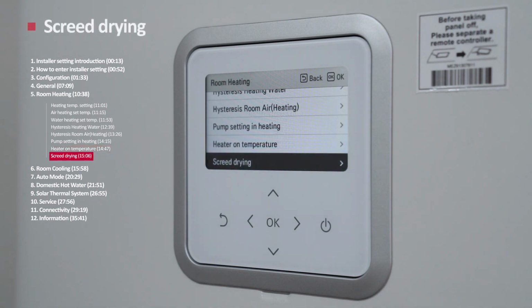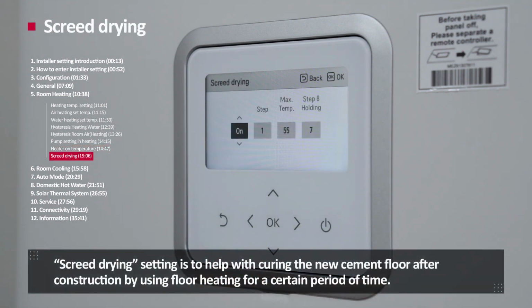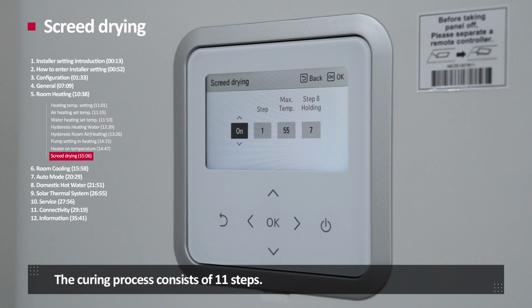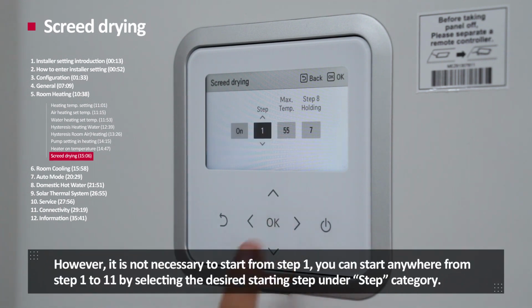Screed drying. Screed drying setting is to help with curing the new cement floor after construction by using floor heating for a certain period of time. The curing process consists of 11 steps. However, it is not necessary to start from step 1. You can start anywhere from step 1 to 11 by selecting the desired starting step under step category.